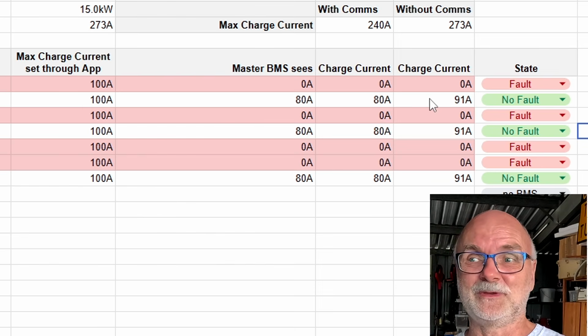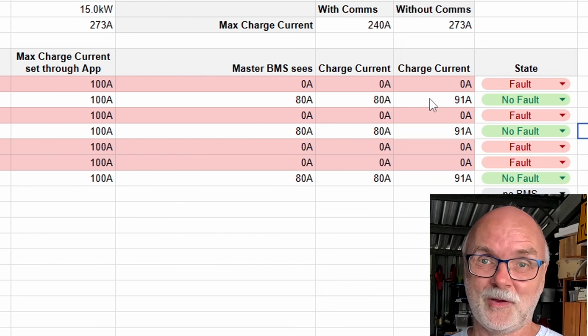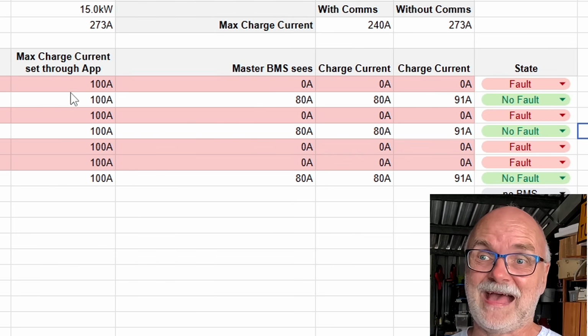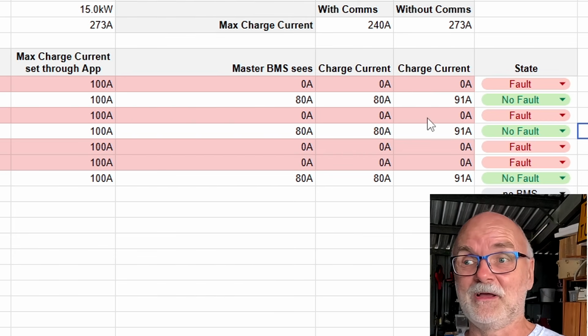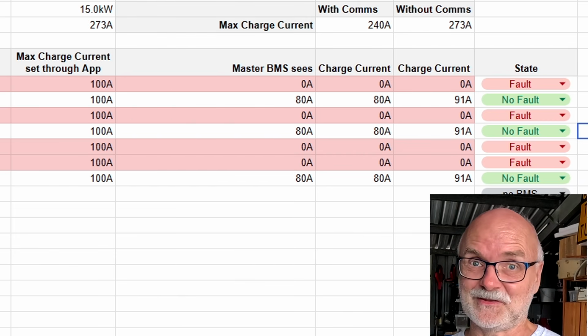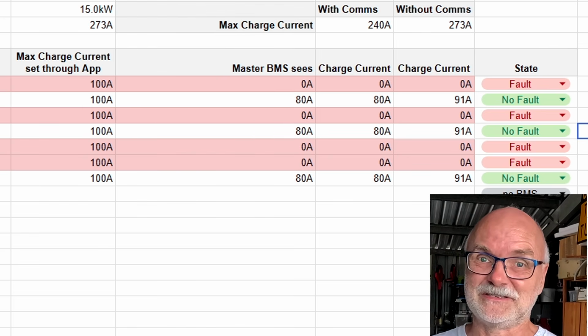Without communication, we are still at 91 amps per BMS. Still safe under the 100 amps. So you can see the larger the system gets, the more batteries you have connected, probably the safer your system will be.